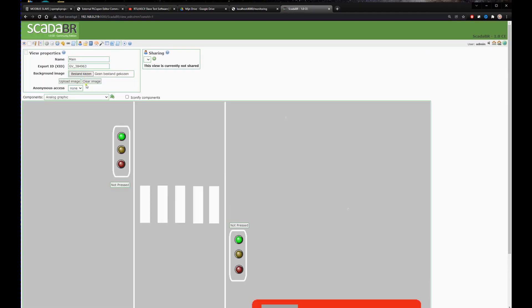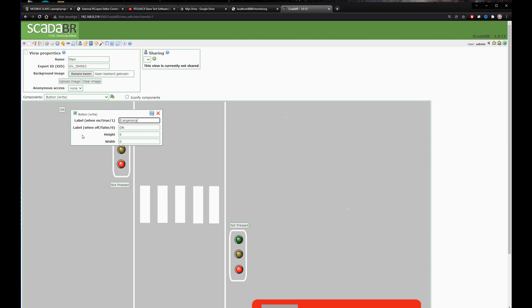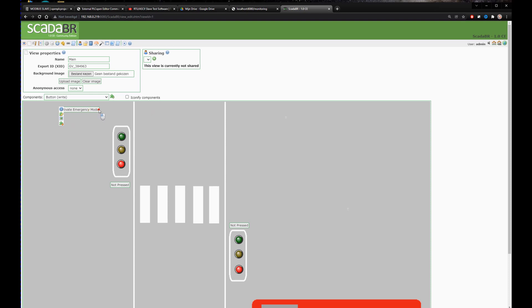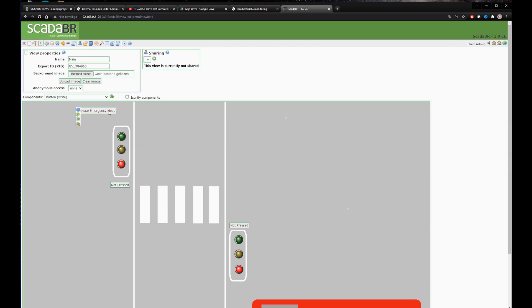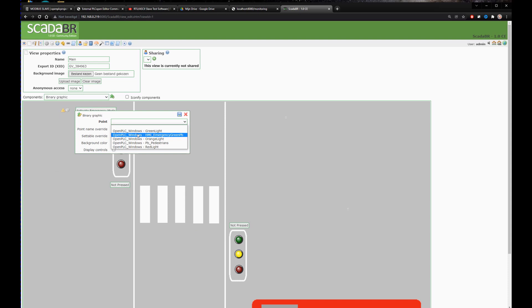Now we'll add the HMI button for emergency services. We choose 'Button Write' and connect the tag. For the text when it's on we'll call it 'Emergency Mode Active', and when it's off, 'Activate Emergency Mode'. It can be tricky to name buttons correctly so you know when they're active. I also change the text height and width so it becomes more visual, since it's an important button. When the button is pressed, the lights will turn to green automatically. We'll also add a flashing light that activates when emergency mode is on, so nobody forgets to turn it off.